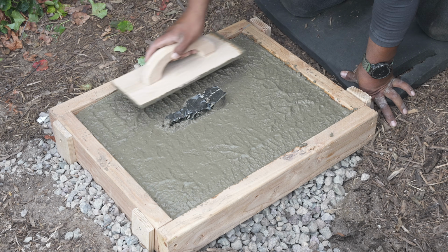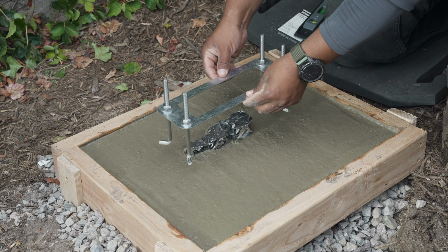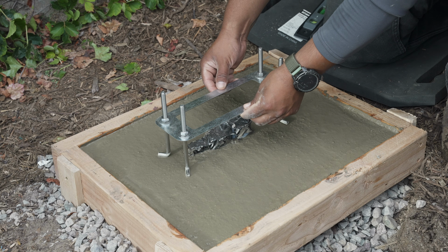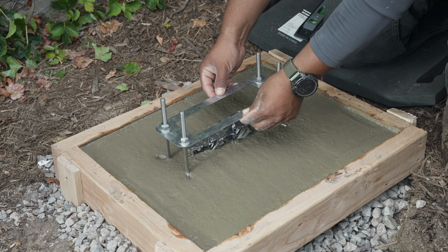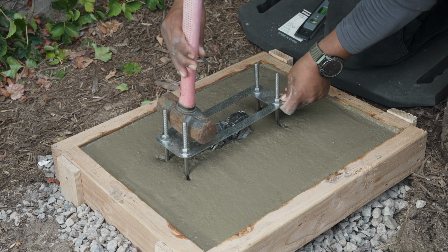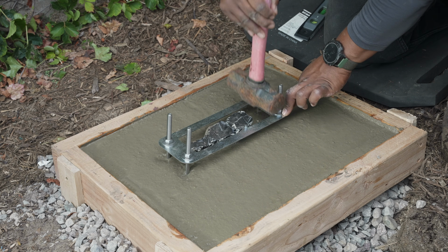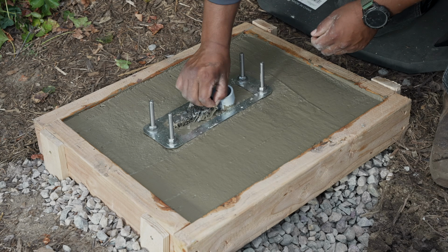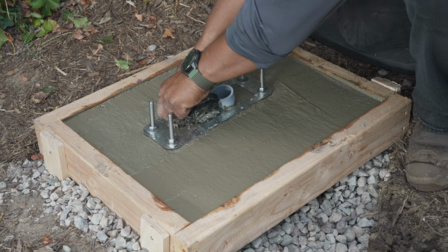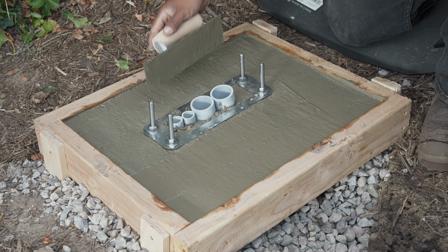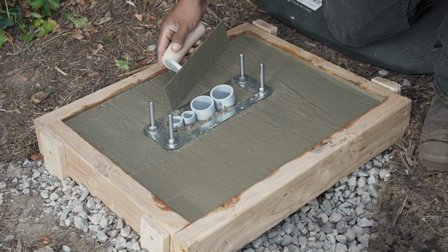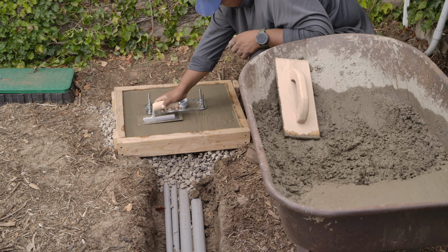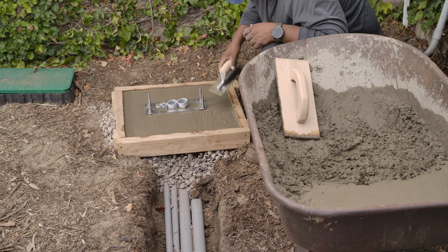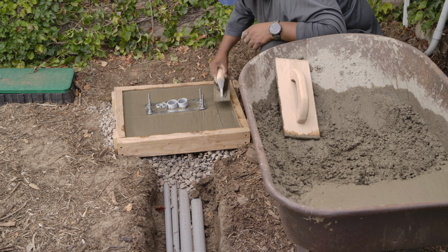smooth the concrete surface. Assemble the pedestal mounting hardware and lower the assembly into the concrete so that the conduits stick up from the center opening. Remove the tape from the conduit and clean up any misplaced concrete before the concrete dries. You may also choose to do a final pass smoothing the surface while the concrete is still soft.